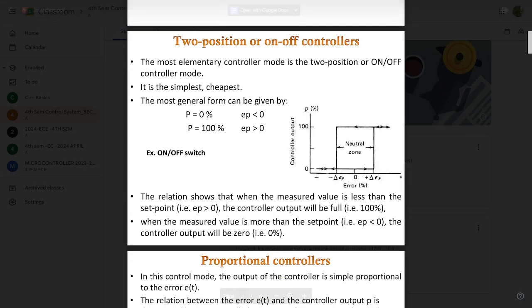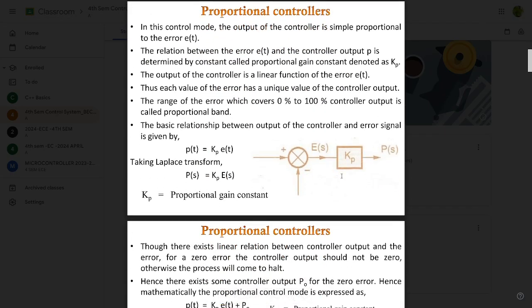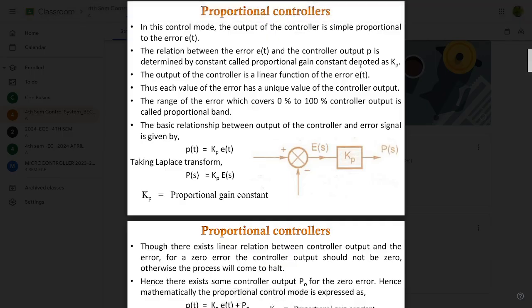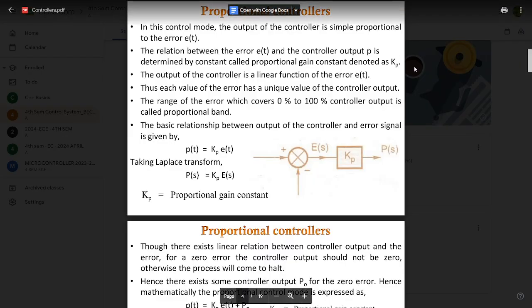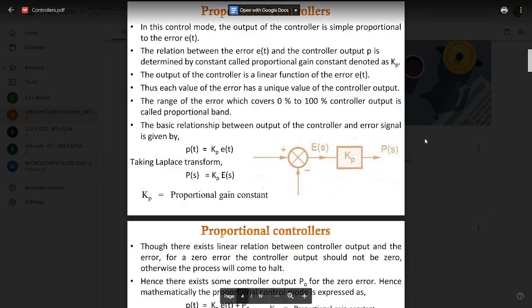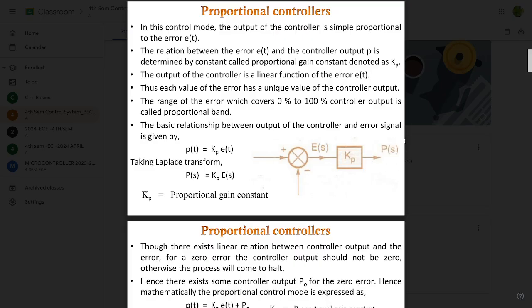The next type is proportional controllers. In this control mode, the output of the controller is simply proportional to the error e(t). The relation between e(t) and the controller output p is determined by a constant called the proportional gain constant, denoted as Kp. The output of the controller is a linear function of the error e(t), meaning each value of the error has a unique value of the controller output.